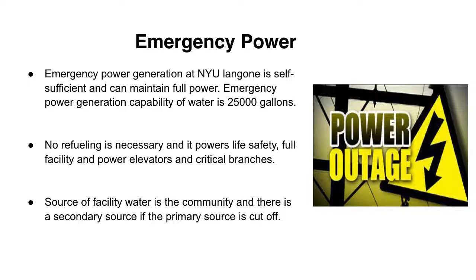In terms of an emergency, there has to be some emergency power generation. Fortunately, NYU Langone has its own energy building, which is located at East 33rd Street and FDR Drive in Manhattan. It is a centerpiece of NYU Langone's Resilient Medical Center program, and it is self sufficient and can maintain full power. No refueling is necessary, and it powers life safety, the full facility, and powers elevators and critical branches. The source of facility water is the community one, and there is a secondary source if the primary source is cut off.